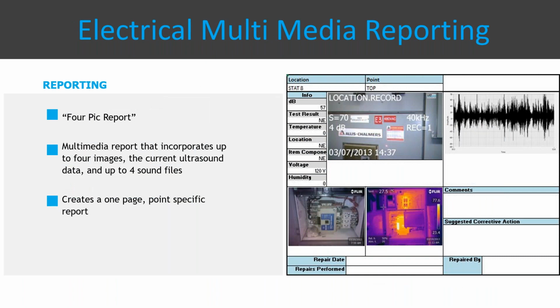We can do the same multimedia reporting regardless of whether you use handheld ultrasonic tools or remote condition monitoring tools. We have the ability to import pictures of the wave files, whether it's a spectrum or time waveform, and bring in a digital photograph, which is very important for documentation. We've worked with insurance companies that love this, because you can document that you're doing the inspection, since those photographs are time stamped and date stamped, and you can attach a recording that's time stamped and date stamped right to it, showing that the switchgear was in good working condition when it was inspected. We can also bring in things like infrared images, so it's truly a multimedia report. If this report is emailed with the sound file attached, someone can visually see it and also listen to it.